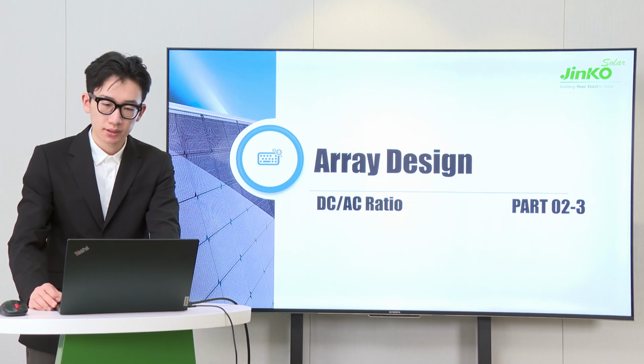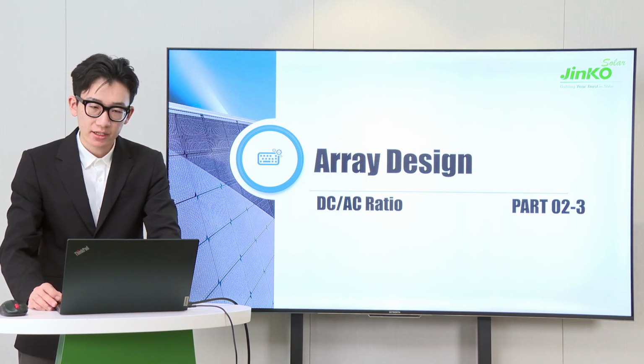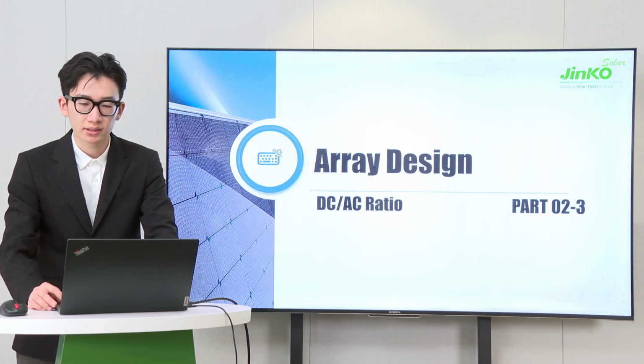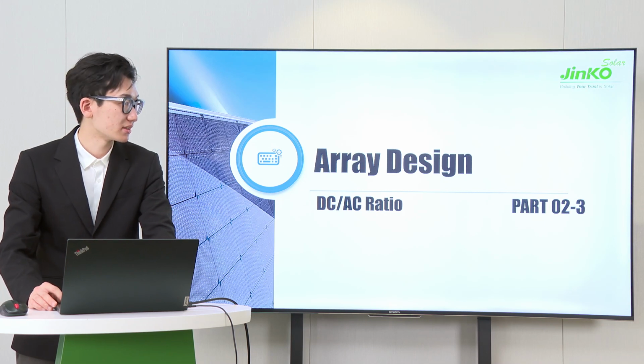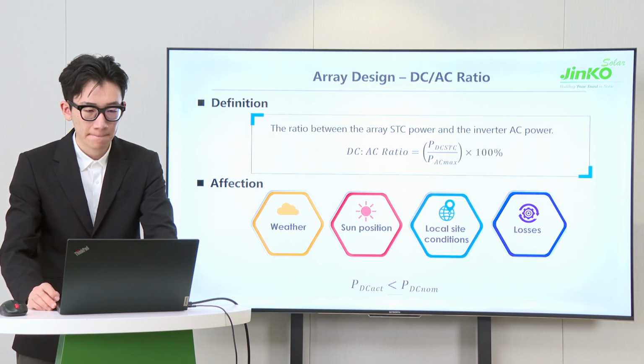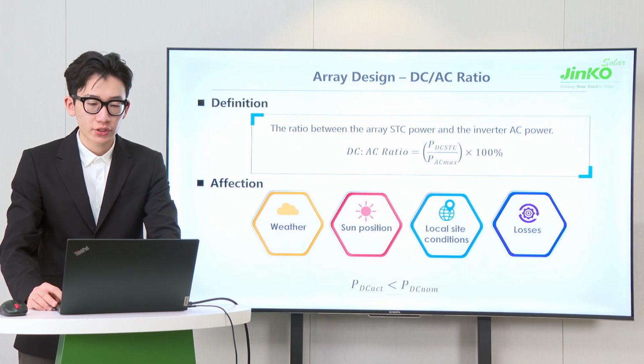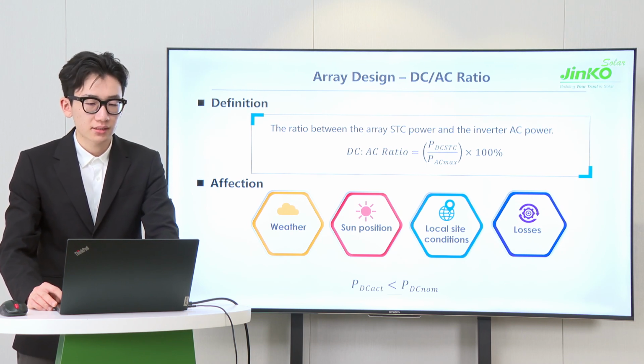When we finish the optimization of tilt angle and spacing, DC to AC ratio is another important design part. The DC to AC ratio is defined as the ratio between the array standard test condition power and the inverter AC power. PV modules do not consistently perform at their nominal output rating.